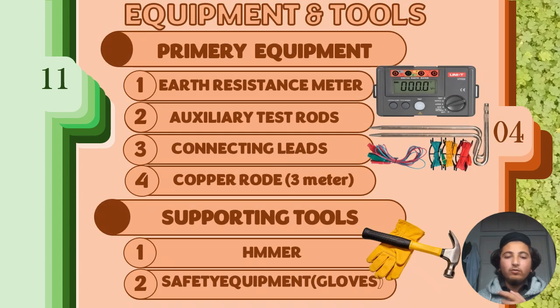Now the equipment and tools used during earthing. Primary equipment is the earth resistance meter, auxiliary test rod, connection lead, and copper rod. This is the earthing meter, this is the auxiliary rod, this is the connecting lead, and this is the copper rod - in this scenario we are using a 3 meter copper rod - and supporting tools like hammer, safety gloves, and many other things used in the whole process.